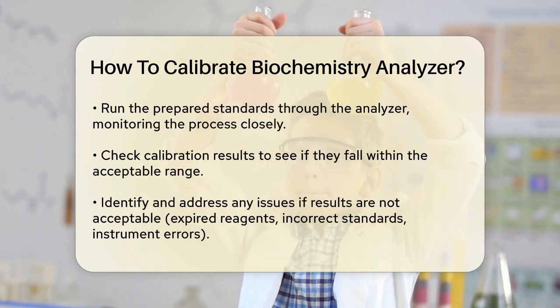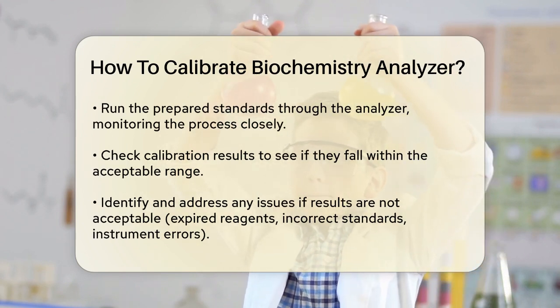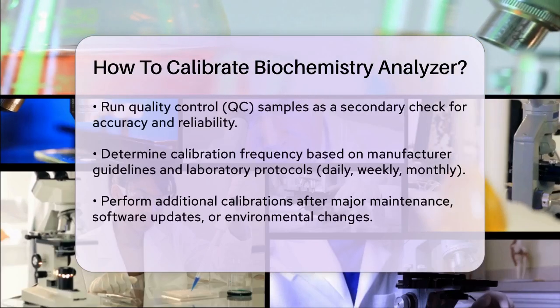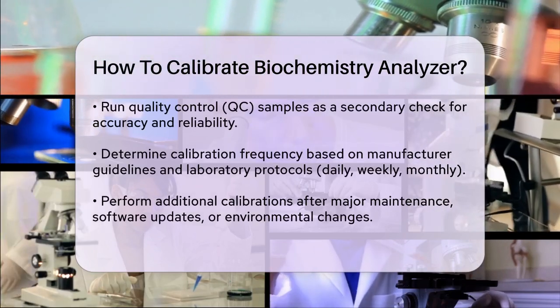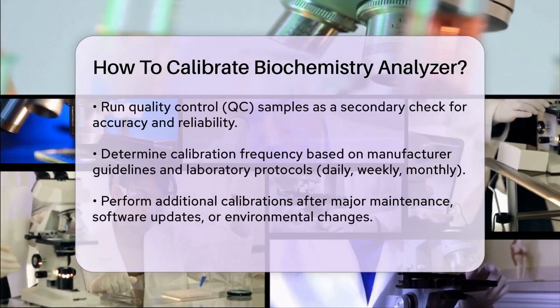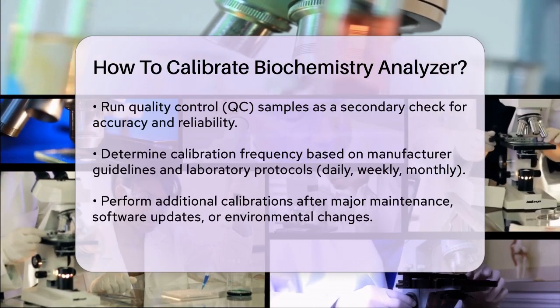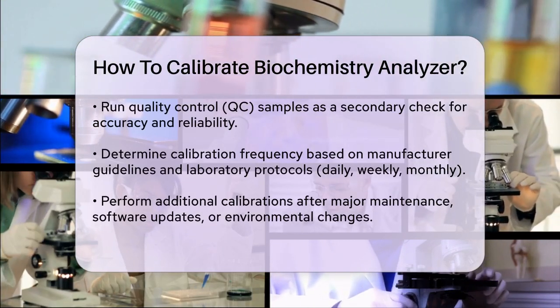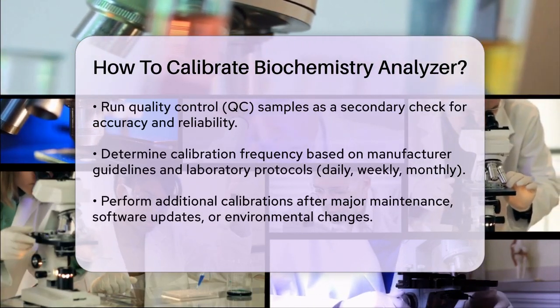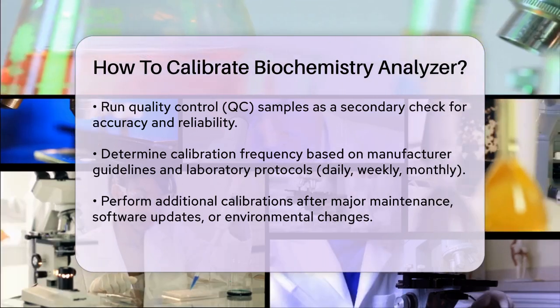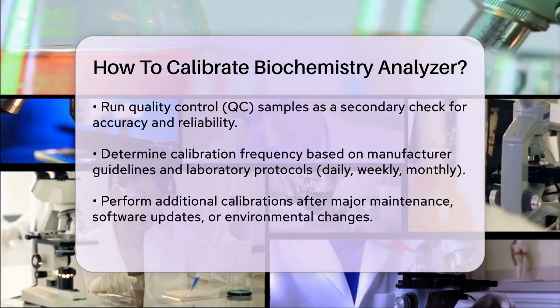In addition to the initial calibration, regular calibration is essential. The frequency of calibration depends on the manufacturer's guidelines, the specific analyzer in use, and the laboratory's protocols. Typically, calibration is performed daily, weekly, or monthly. Additional calibrations may be necessary after major maintenance, software updates, or changes in the analyzer's environment.